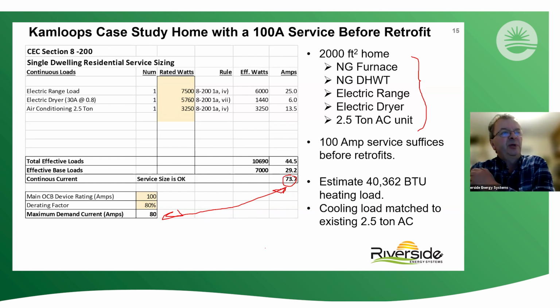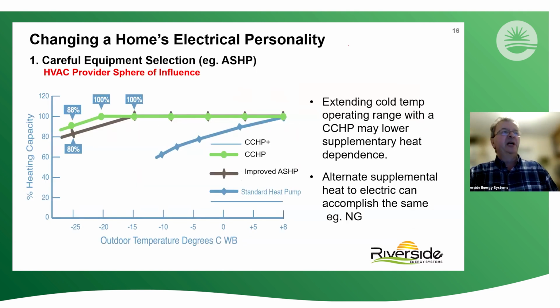So now if I was to contemplate an energy retrofit, and the example I picked was adding an air source heat pump, we can see that potentially I'm going to run into trouble. So let's look at what I can maybe do to change the home's electrical personality. So the first thing we can do is we can carefully select equipment. So some of the other speakers, in particular Gary Hamer, is going to tell us, and very rightly so, that not all air source heat pumps are created equally. So, a garden variety heat pump will have its efficiency droop, like this, so that beyond about -10, its mechanical advantage, coefficient of performance, will have dramatically dropped, and it's not going to be much good, and we'll be needing supplementary heat to help us out.